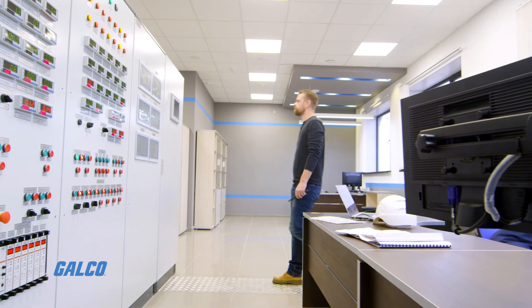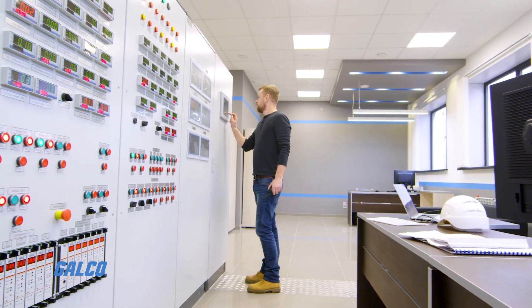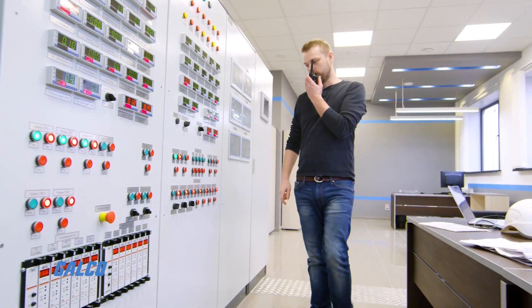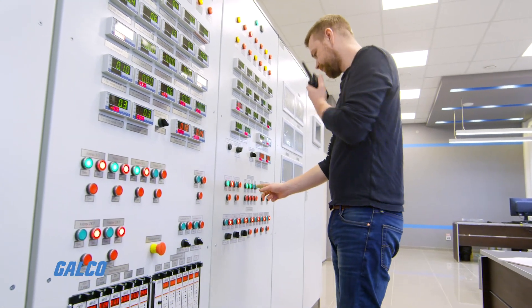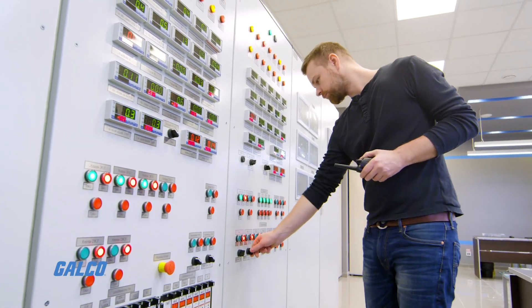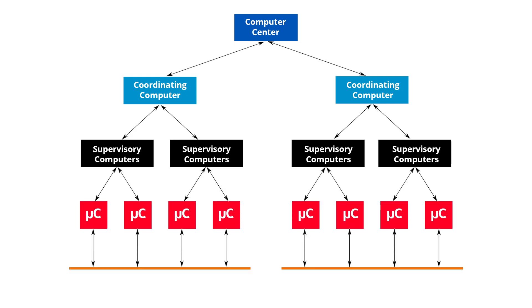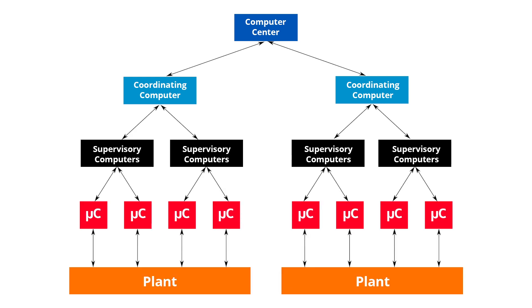A DCS consists of numerous local controllers in various sections of a plant control area, and are connected via a high-speed communication network. In DCS control systems, data acquisition and control functions are carried through multiple DCS controllers, which are microprocessor-based units, distributed functionally and geographically over the plant, and situated near areas where control or data-gathering functions are being performed.